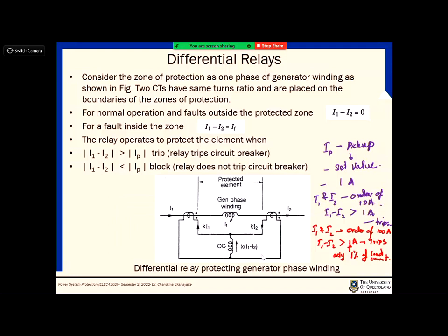So it is quite easy to implement, as you can see here, for normal operation or fault outside the zone. So what happens now is, which zone is protected by this sort of differential scheme? That is also important, right?